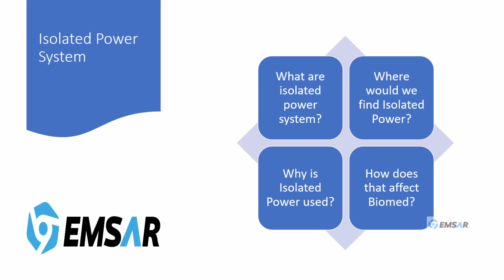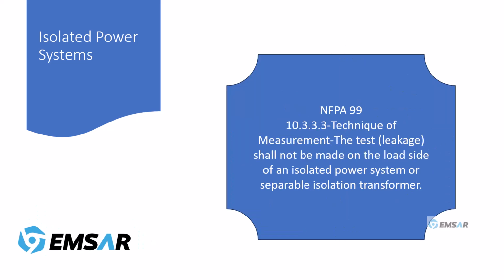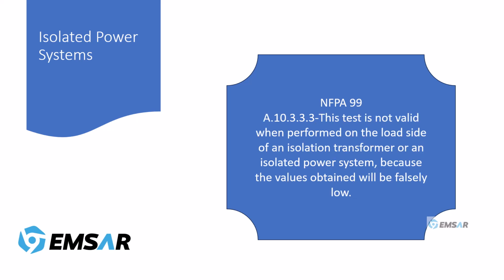Furthermore, NFPA 99 requires wet procedure locations to have special protections against electric shock. These special protections affect biomed because biomed needs a well-grounded outlet in order to perform electrical safety tests. So NFPA 99 requires biomeds not to perform electrical safety testing on the load side of an isolated power system or a separate isolation transformer. This is because the test will not be valid when performed on the load side of an isolation transformer or isolation power system, because the values obtained will be falsely low.